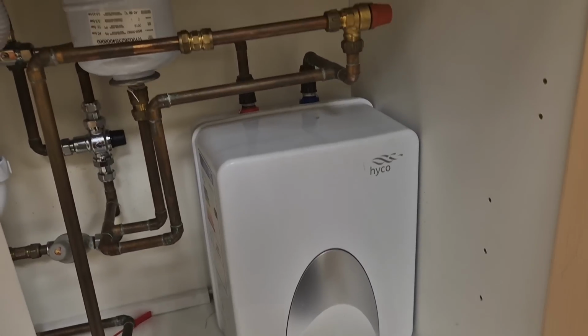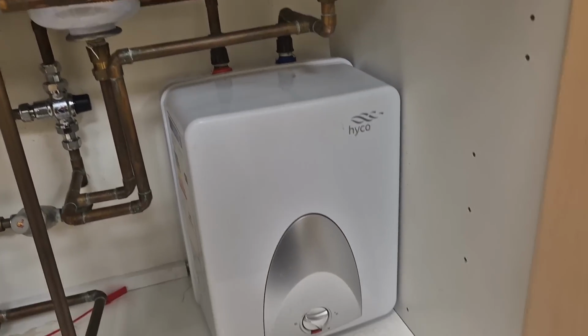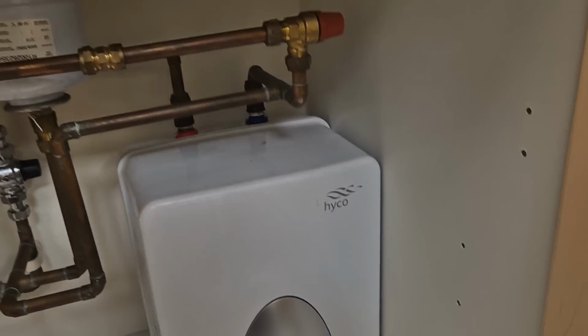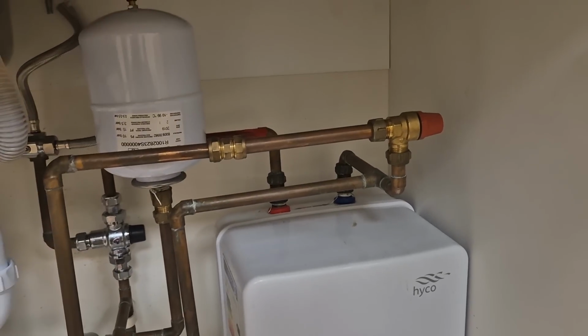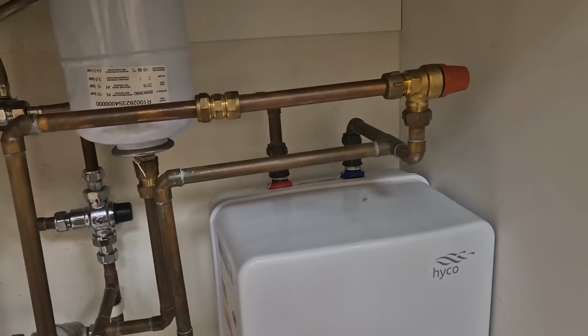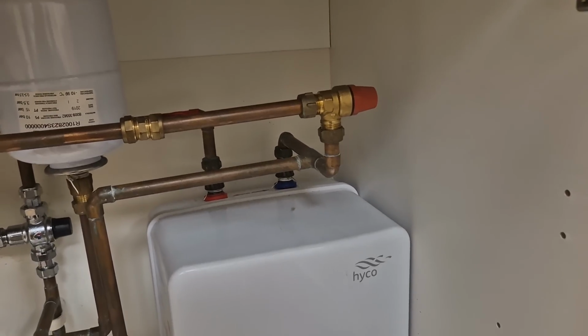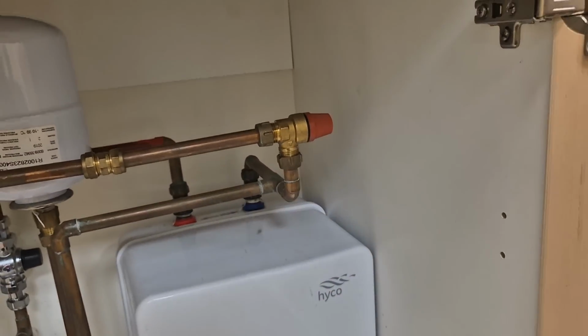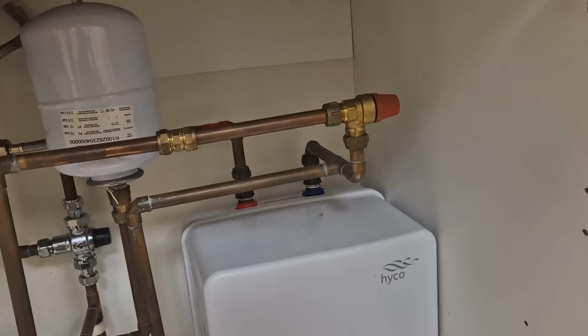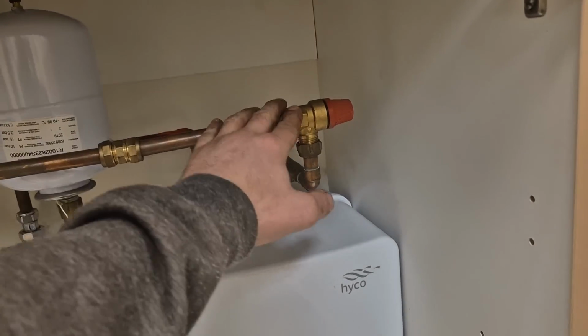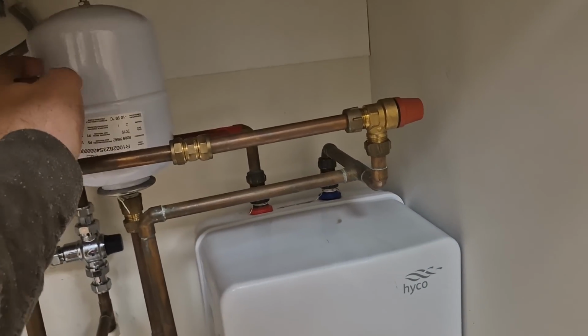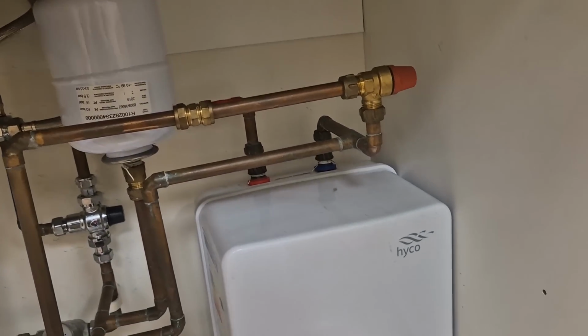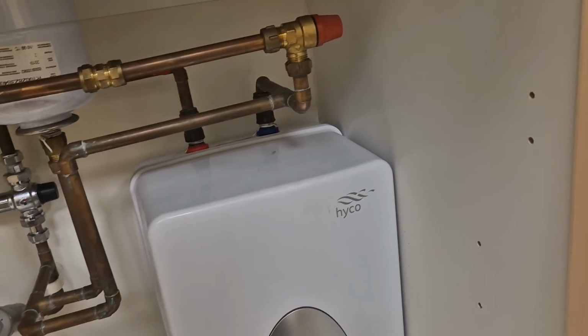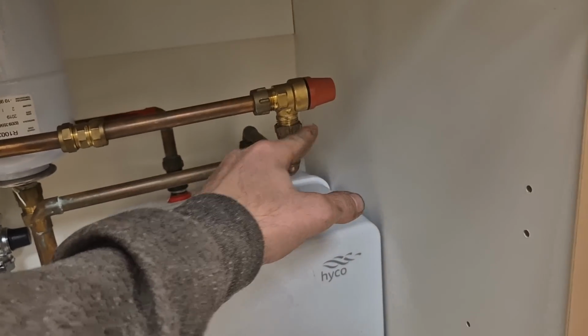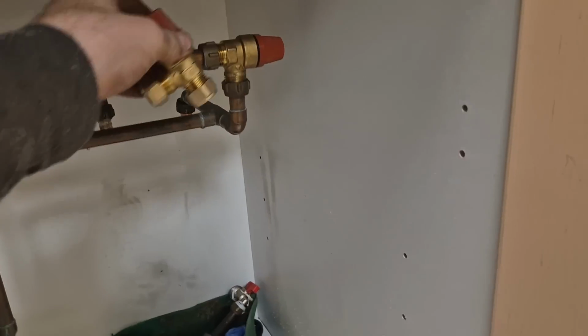Can anybody spot the fault on this heater? This thing's blowing up and water's gone everywhere, but can anybody spot the fault with it? Because the first thing I saw when I walked in was the issue. Yeah, that, so back to front, not very good. I'm going to put a new expansion vessel, change that bit. I'm changing the whole heater. That expansion vessel's probably fat. I picked a new one of them up, but yeah, it'd be a straight swap. Hyco 10 litre, but yeah, that looks newer than the heater. It should go that way, not that way.